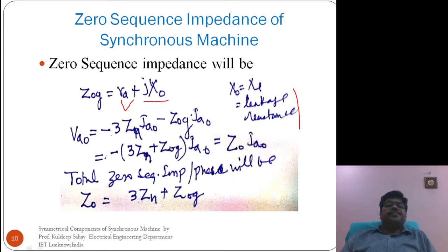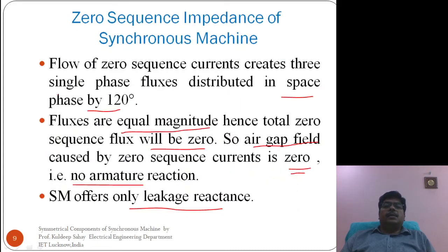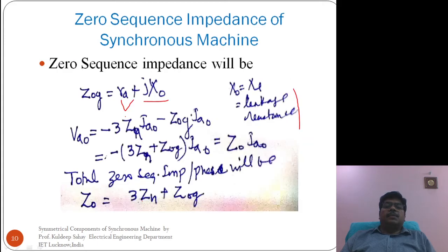So here, how do we determine the zero sequence impedance? It can be done manually through an autotransformer. A prime mover is not used in this case. In a laboratory, we can rotate the rotor by hand. The field is short circuited, while all the armature windings are connected.